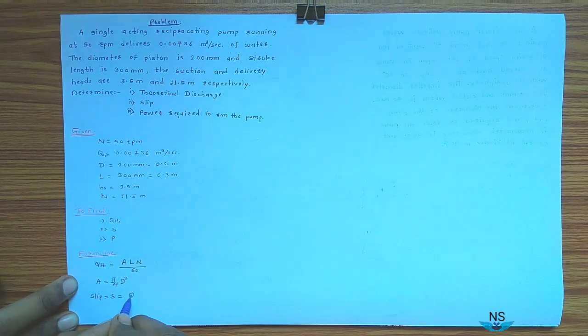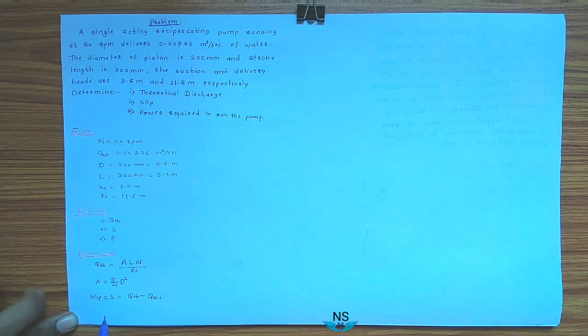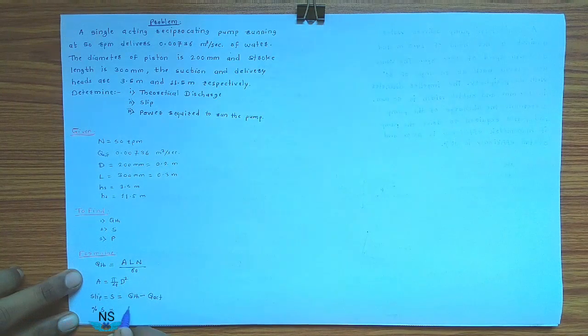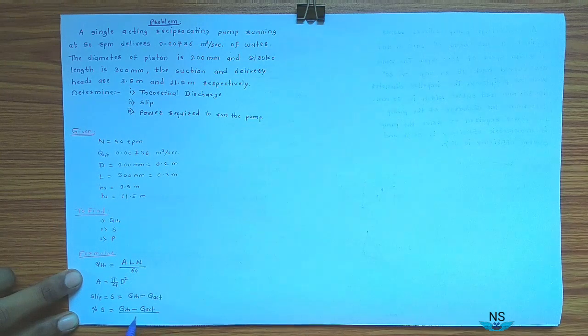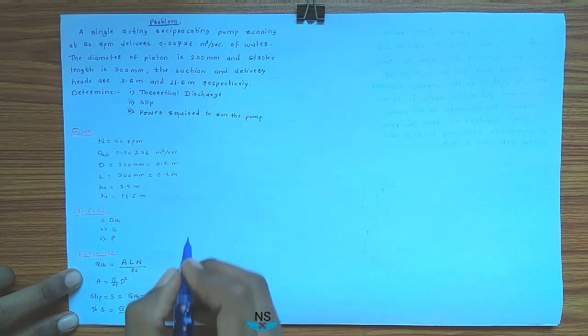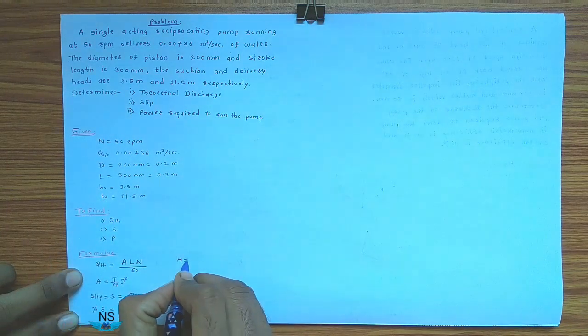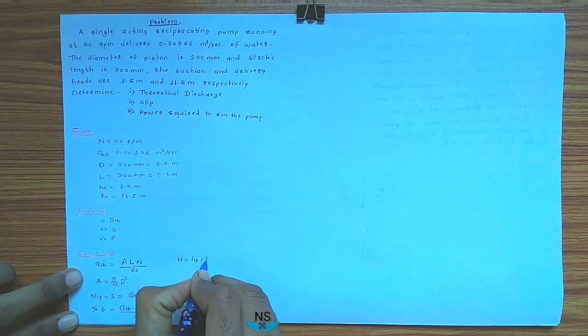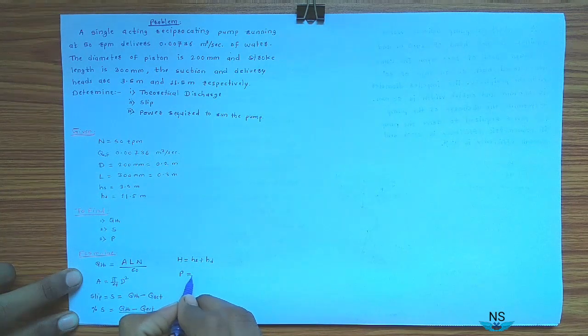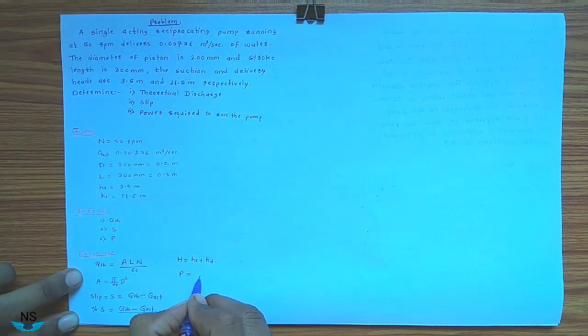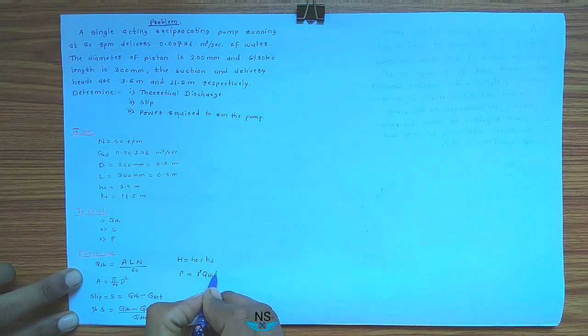Slip S is equal to Q_theoretical minus Q_actual. Percentage slip is equal to (Q_theoretical minus Q_actual) divided by Q_theoretical, into 100. Total head H is equal to suction head HS plus delivery head HD. Power required to run the pump P is equal to γ (gamma) into Q_theoretical into H.